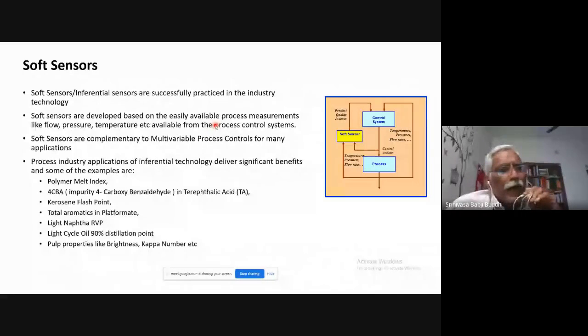And these soft sensors or inferential sensors are complementary to the multivariable process controls in many applications. In many applications, particularly in advanced process control, the focus will be how to improve the quality control, how to reduce the variation in the product quality. For that, if you do not have a measurement, then it becomes really impossible for the control strategy to control it. So since the laboratory information is available only once in 4 hours or once in 8 hours, this soft sensor will provide the advanced control strategy useful information about the quality every few seconds. So that's why it has been successfully used in conjunction with advanced process controls in many industries.